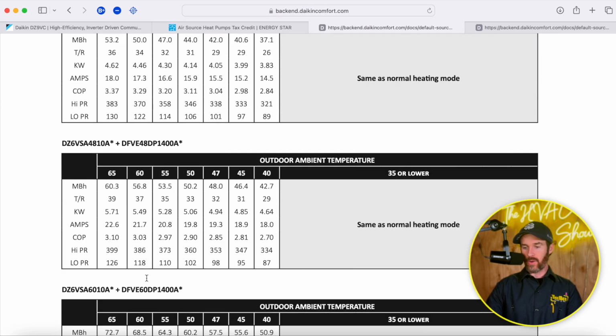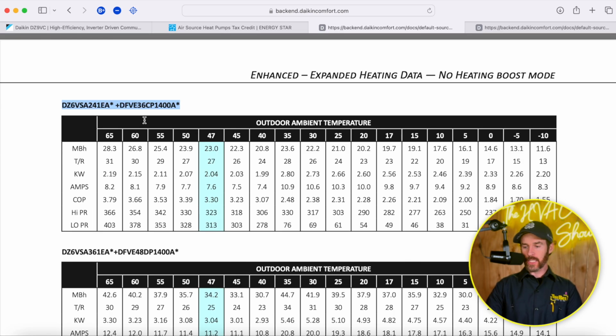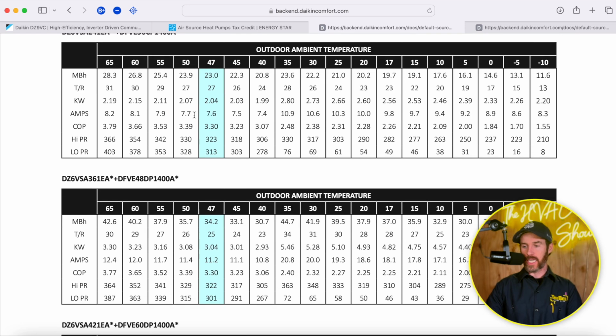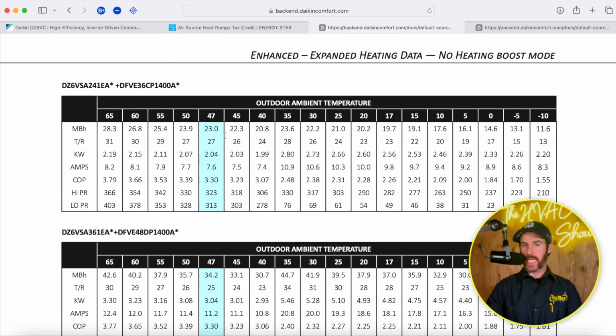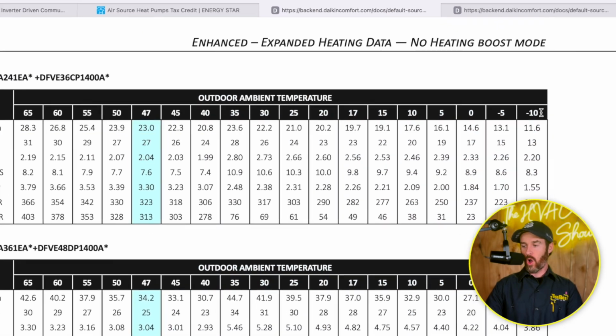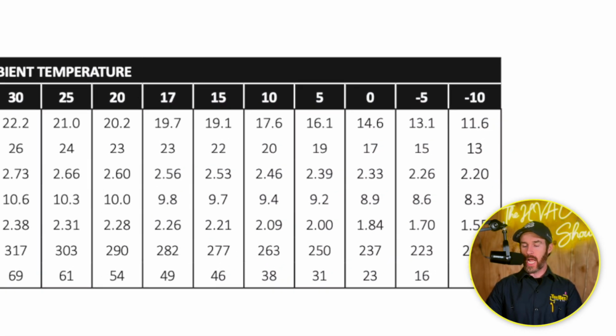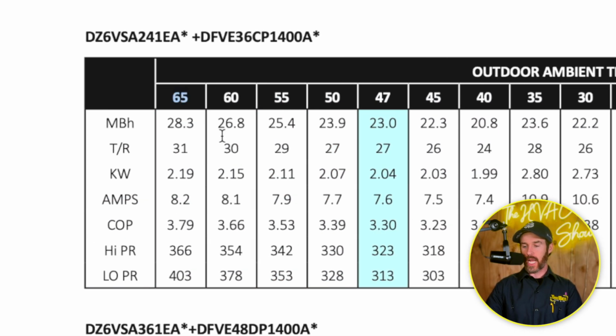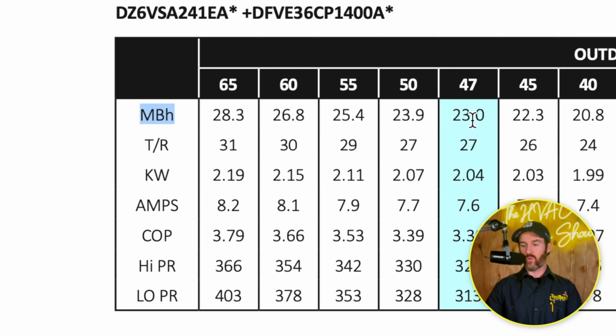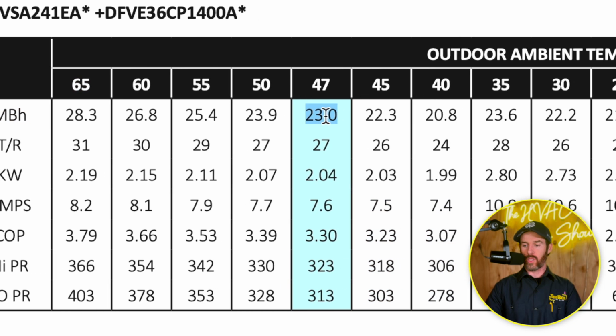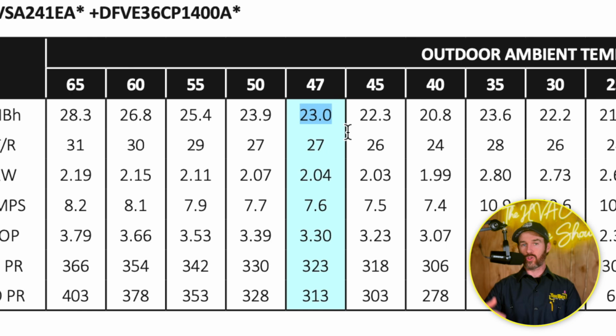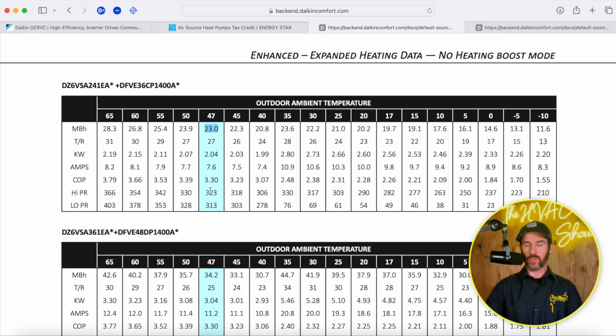Now, if we go down here, so this is the 2-ton system, and just to give you a head-to-head matchup so you can see what this chart means, just to demystify it. This number at the top is the outdoor air temperature. So it goes all the way from negative 10 degrees Fahrenheit up to 65 degrees Fahrenheit. This MBH stands for thousands of BTUs. And so this 23 means 23,000 BTUs, which is about 2 tons of heating capacity.